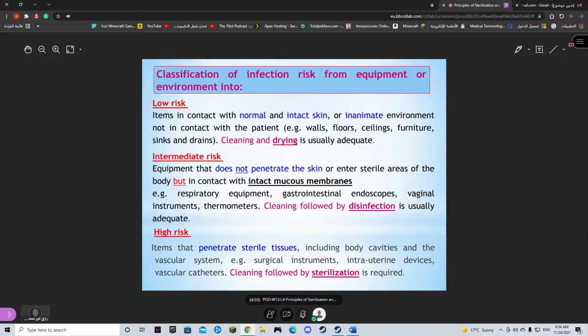For example, ethylene oxide is a gas you use for cleaning syringes and catheters, because you are not meant to put a catheter in something hot for cleaning. So we have a special method for this. Ethylene oxide is highly carcinogenic and highly explosive in nature. It will blast if you use a high concentration of it. So these are the intermediate and high risk things, and you have to be careful about how you use it and how much concentration is allowed. How much is tolerable for humans and how much is protecting the environment?